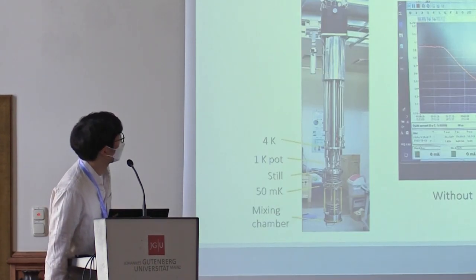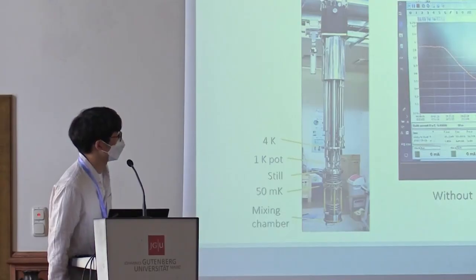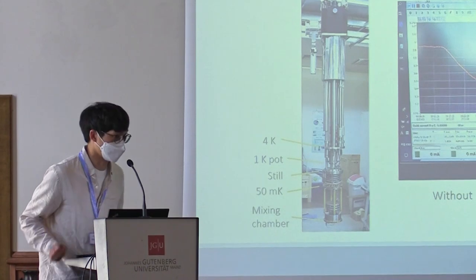Our dilution refrigerator from Leiden Cryogenics achieved a base temperature of 5.4 millikelvin without load. After mounting the cavity, the mixing chamber sits around 22 millikelvin. In the presence of the magnetic field, the cavity and mixing chamber are in the 20s millikelvin range.